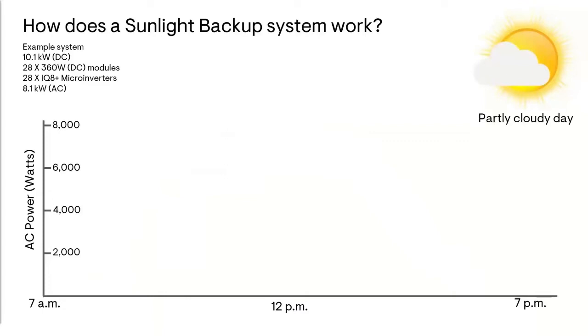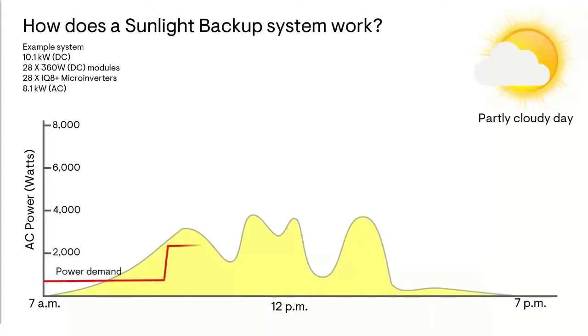Now, what about clouds? On a partly cloudy day, the available power of the solar array is going to fluctuate a lot as clouds periodically block the sun. If the home's power demand ever exceeds the power of the solar system, the microgrid will collapse and power will turn off. After a few seconds have passed, the system will attempt to form the microgrid again. If the available power can handle the demand at that moment, then it will successfully start up. But if the demand still exceeds the available solar power, it will fail again. Repeated attempts will be made over increasing time intervals to allow the solar system's power to hopefully increase if the clouds move out of the way of the sun, and hopefully the homeowner will be aware of what's happening and will reduce their power demand by turning off loads as well.